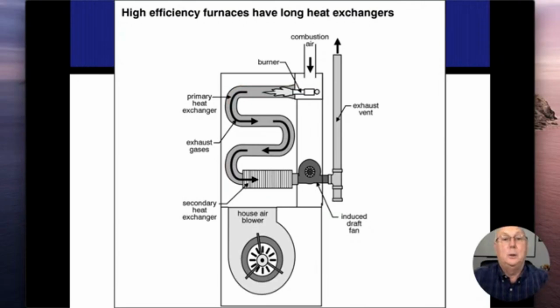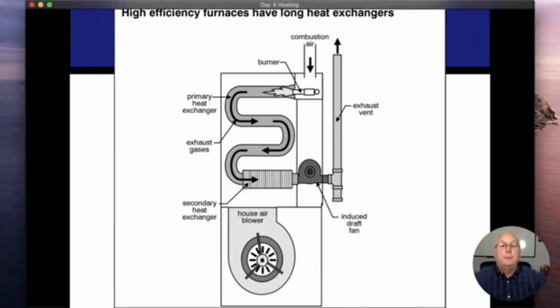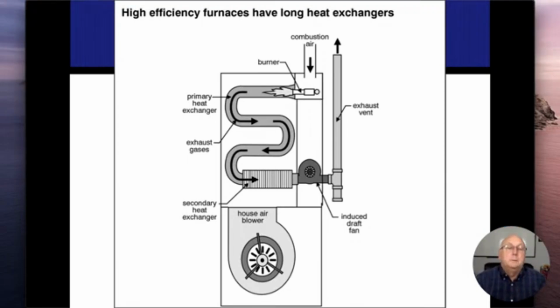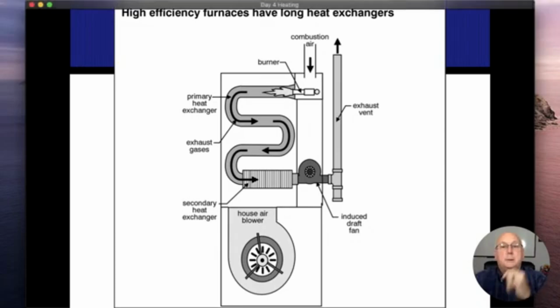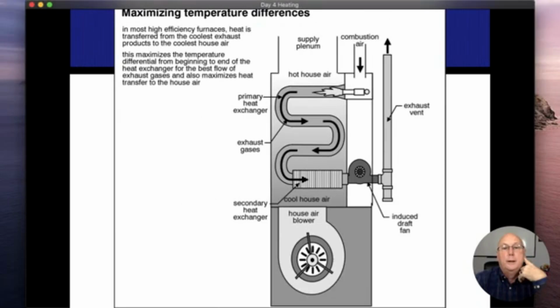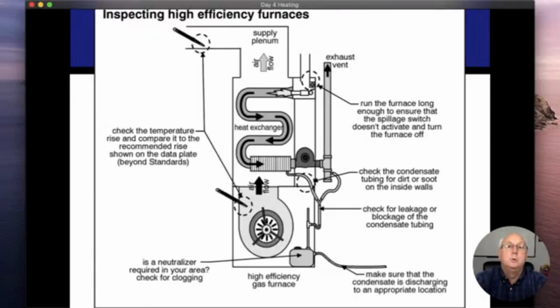Just a telltale sign. So as the air runs up where the blower fan is, it's going to be room temperature. It's going to absorb most of its heat through the secondary heat exchanger. And then as it gets up higher and higher through the primary heat exchanger, those pipes are going to get hotter. So then as the temperatures equalize out, that's how it absorbs as much heat as it does. And that's what this drawing here is trying to show. So it's colder here on the outside and everything starts getting warmer. It's hottest here and it starts losing the heat as it gets colder. And basically that's how a high efficiency can be so efficient.